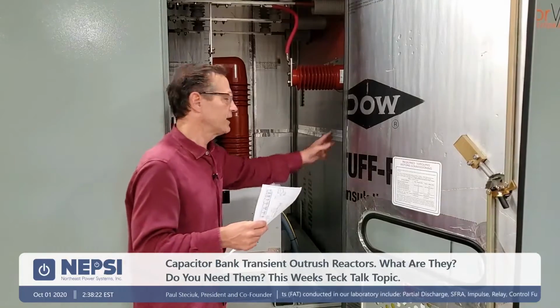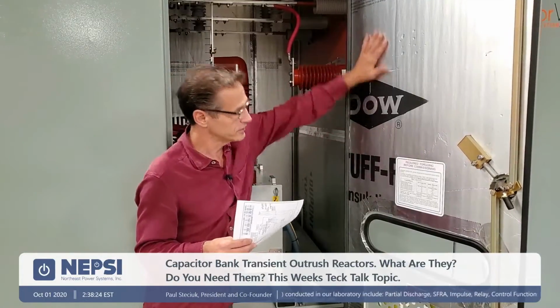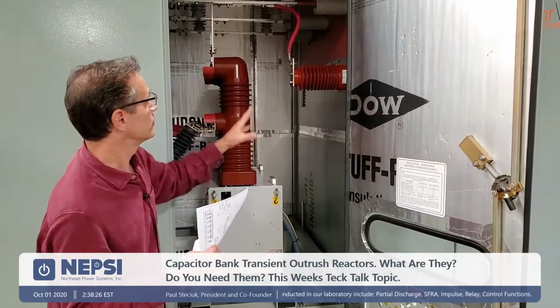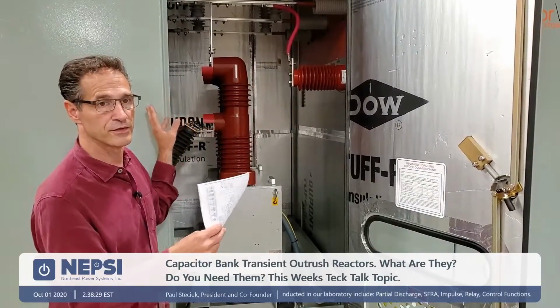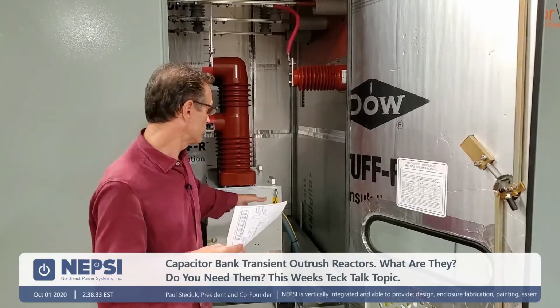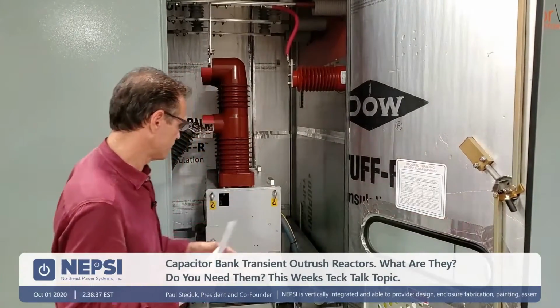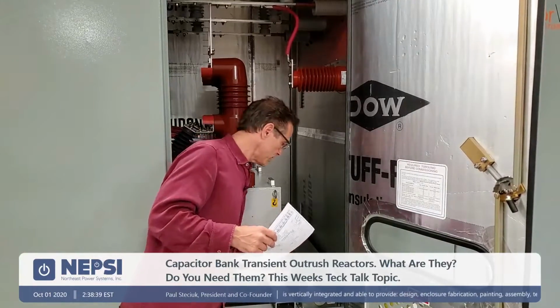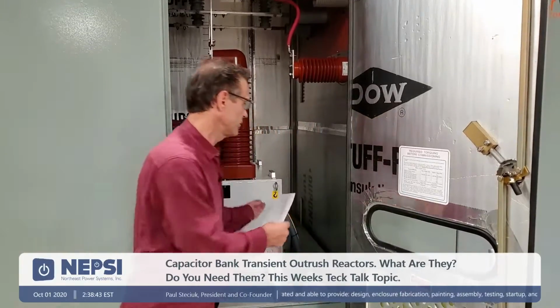So we're looking to maintain the environment inside here. So we insulate this complete compartment. We use through-wall bushings between the compartments, and we heat this compartment to a temperature that's within the rating of this device, plus some for margin. And that's really the purpose of that. It's easy to change out. You've got a quick connect here that you can release to pull the device out.